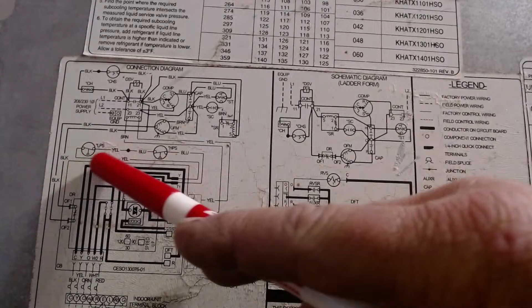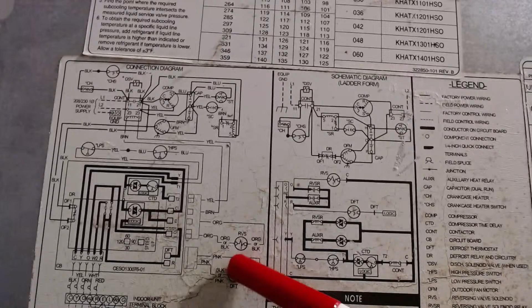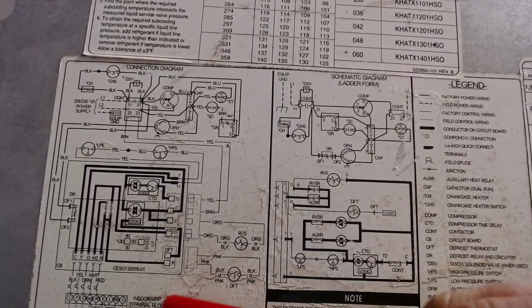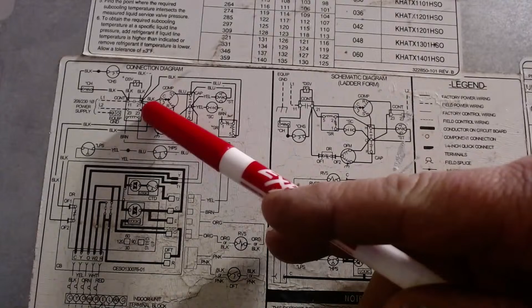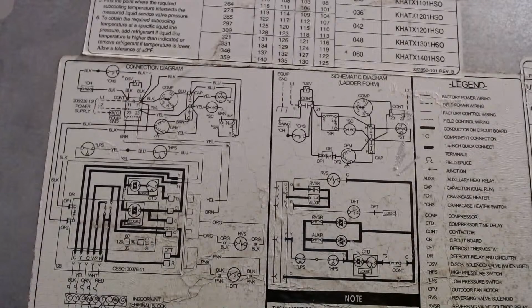So we'll go back through real quick. Here's our low pressure. Here's the high pressure. Defrost sensor, reversing valve solenoid. Up here, 11, 21, 23, 23. This area right here is telling you a lot of information about that contactor immediately. Because we have the 11 and 21, that's telling you have a connection point. That means there's a break, there's a relay, there's a contact there. Hence how it's drawn with the two lines right there. The 23 and 23 tells me there is no contact. It's straight through. If that was a two-pole contactor, it'd be 13 and 23, not 23 and 23. So that's definitely information there.